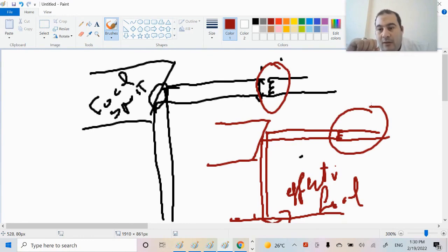I have the option because a small focal spot means the beam of electrons becomes more concentrated. So the resolution quality of the image will be higher compared with long filament usage. When utilizing the short filament, the resulting focal spot size remains compact, and thus the electron beam concentration increases beyond what is achievable with longer filaments.